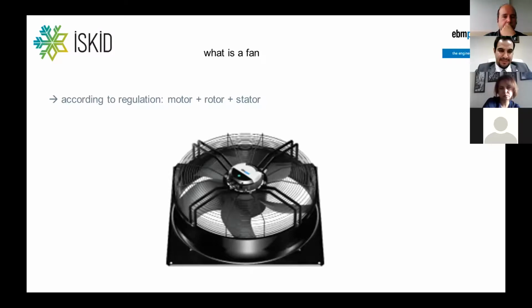But for the time being, a fan consists of at least a motor, a rotor, and a stator. And the stator is not a motor stator. The stator is the stationary parts that are around the fan. So it's minimum the air guiding device, which could be a cone. If it's a backward curve, it's the inlet cone. This is the stator. So we have the rotor, the rotational part, and the stator is the air guiding part.